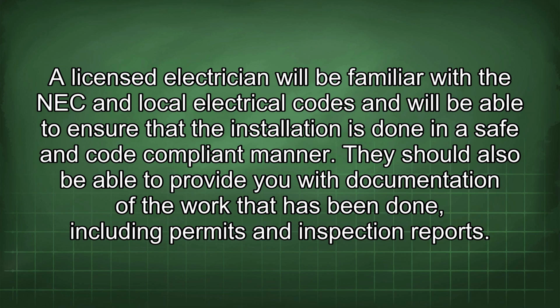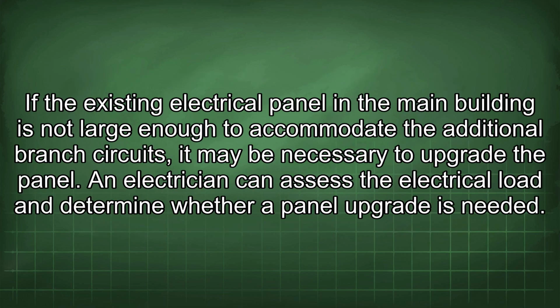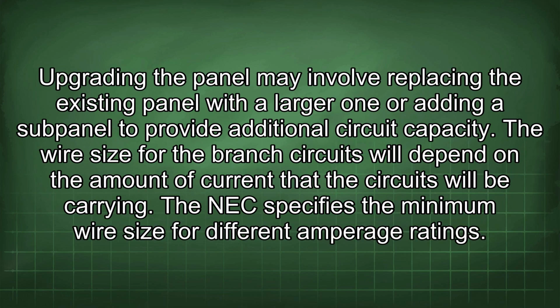inspection reports. If the existing electrical panel in the main building is not large enough to accommodate the additional branch circuits, it may be necessary to upgrade the panel. An electrician can assess the electrical load and determine whether a panel upgrade is needed. Upgrading the panel may involve replacing the existing panel with a larger one or adding a subpanel to provide additional circuit capacity. The wire size for the branch circuits will depend on the amount of current that the circuits will be carrying.